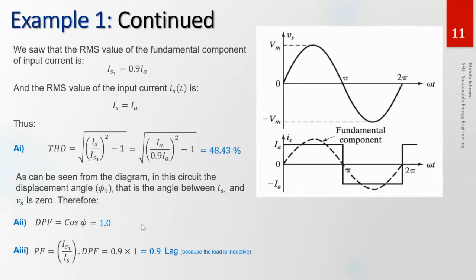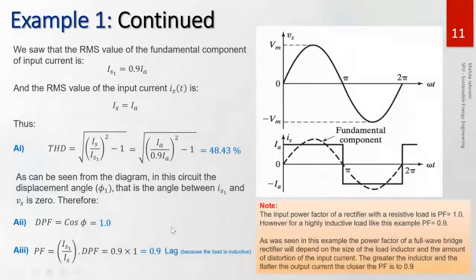And remember, when you're calculating the power factor, you always have to say lag or lead. Without lag or lead, you get half the point. So this is 0.9 lag, and the reason it's lag is because we have a motor as our load. A motor is an inductor, and inductors always create lagging circuits, right? So here we have 90% lag because we have an inductive load.